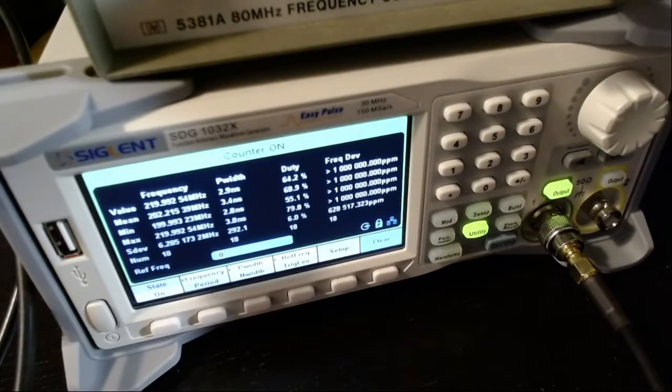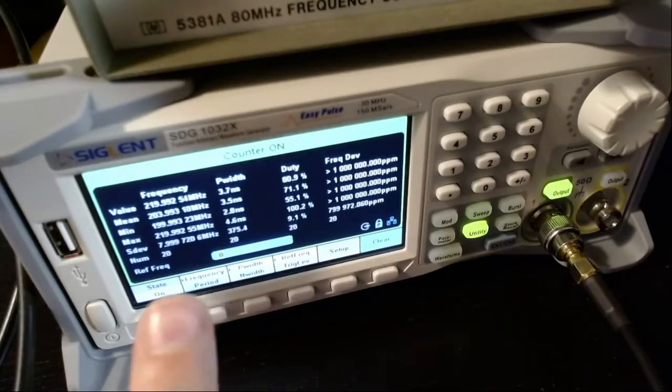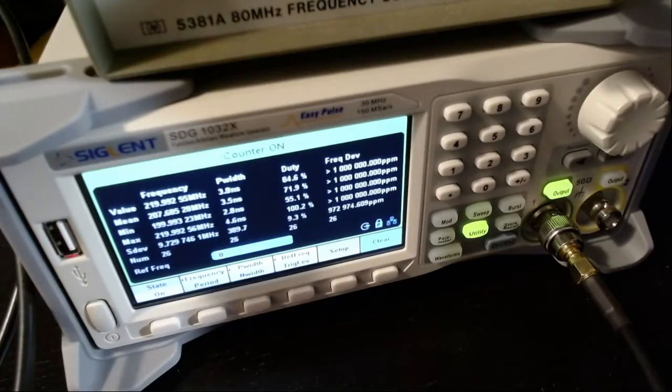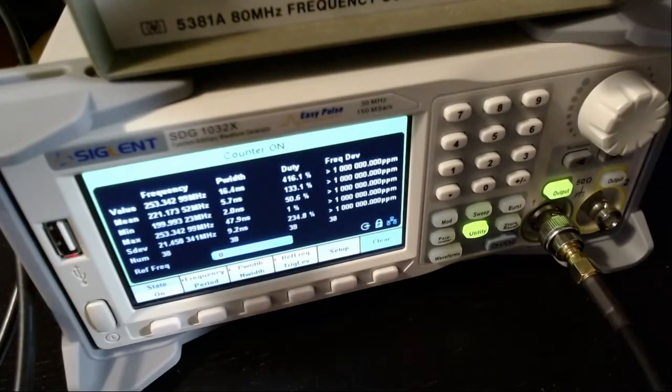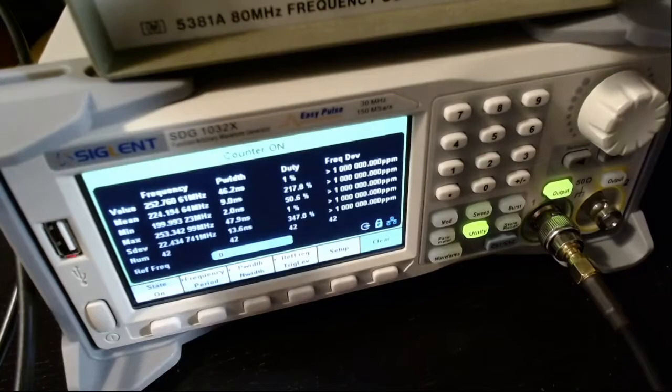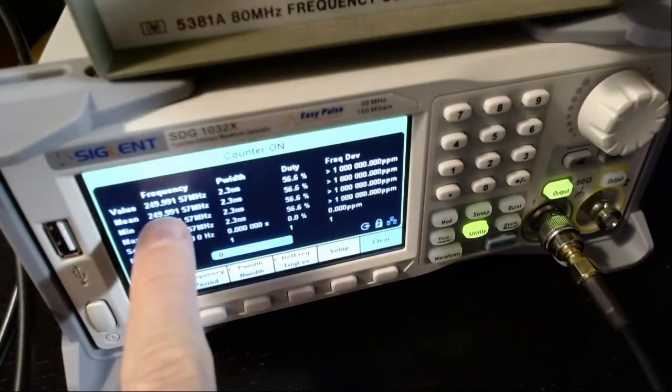It's still reading. Although the specified limit is 200 megahertz, it's actually reading with some accuracy also 220. Let me try 250. Yes, 250, there we are, excellent. Let me try 300 megahertz. I just inputted 300 megahertz and it looks like it's not managing. It's reading 253, so this is above the capabilities of this instrument. I would say the real limit is 250 megahertz. Let me put 250 and clear here, and we get our 250 minus something due to the slight difference in clocks.